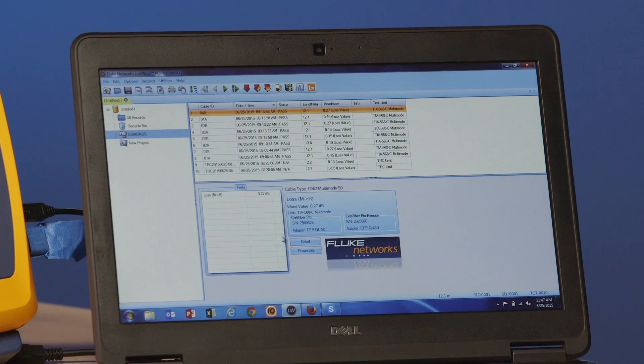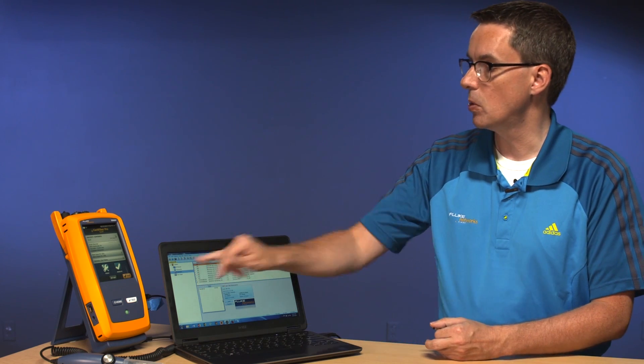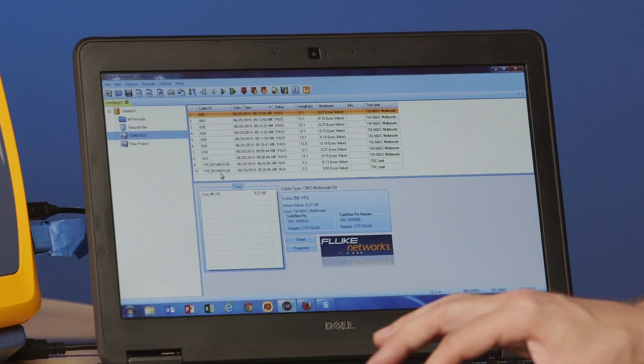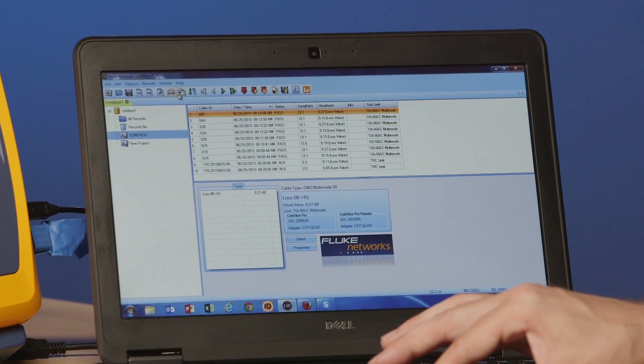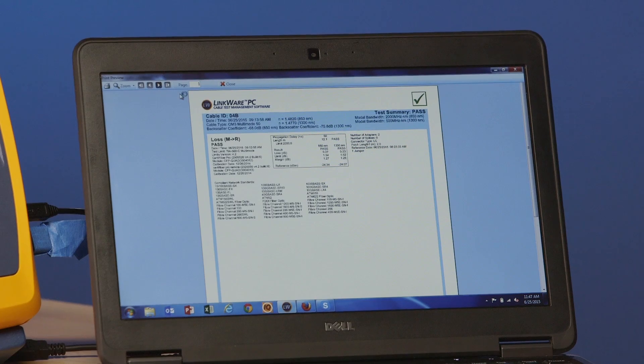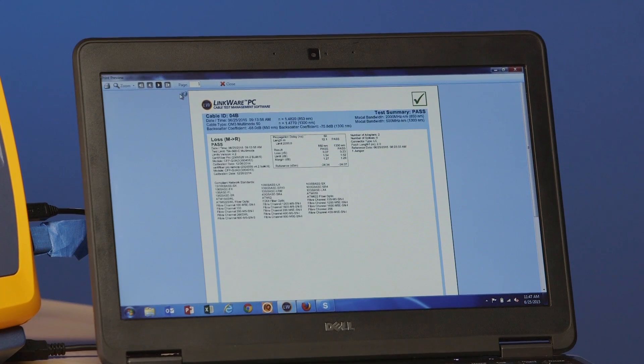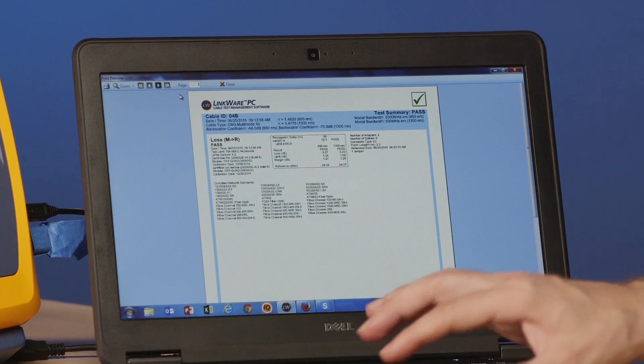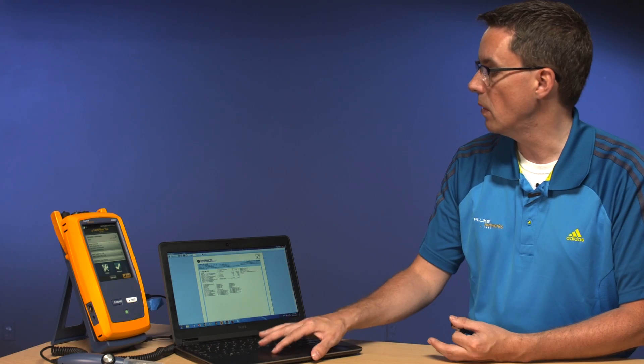Now, when you present these to the customer, it's a good idea to save it in its original format in LinkWare which is .flw and give them the LinkWare file itself. You do have the option over here of creating a PDF report and give them that as well. But we don't really recommend that. Give the original file because it's a lot easier to sort through and if you wanted to do analytics or anything else, it's far easier to do it from the original LinkWare file. You can, of course, preview any of these test results here. And here is an example of the test report that you'd get from the CertiFiber Pro. So that's one way of getting our test results. Let me close down this window here.